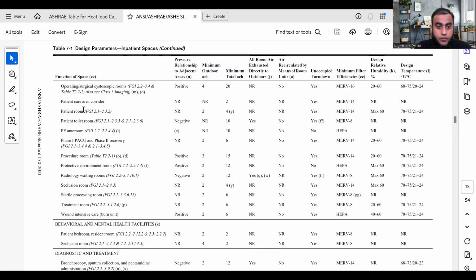I'm talking about, okay, where is patient room? Here. Even see, minimum filter efficiency is given and maximum relative humidity, which is design relative humidity, is given 60%. And how much temperature? Design temperature between 70 to 75 degrees Fahrenheit. In degrees Celsius, 21 to 24. So is it clear? Yes, tell me please, all of you. So this is all about it.